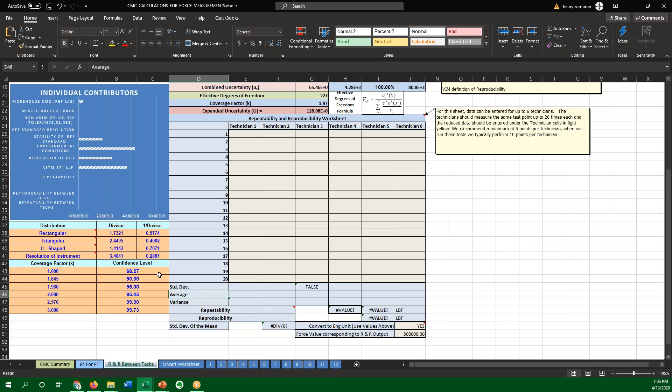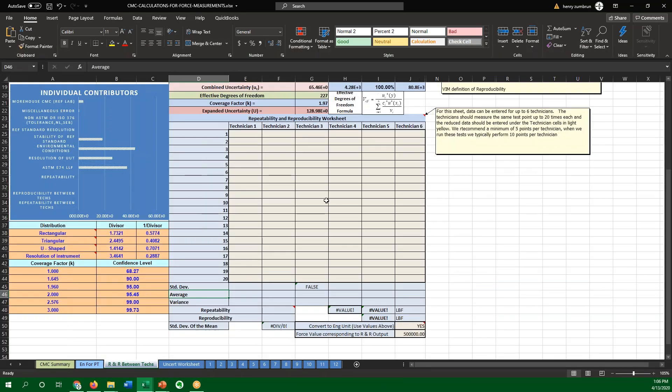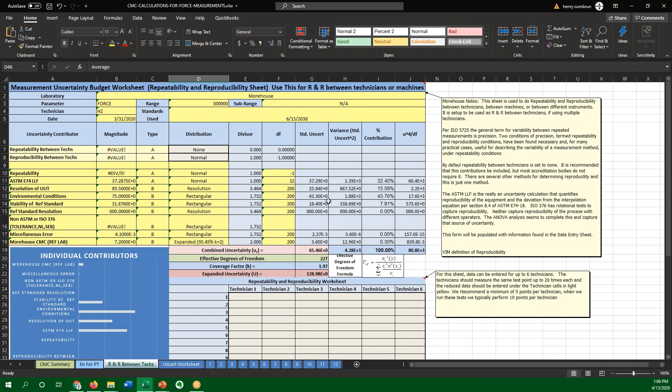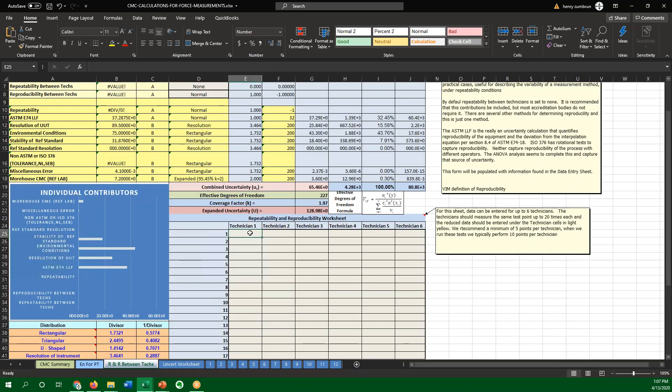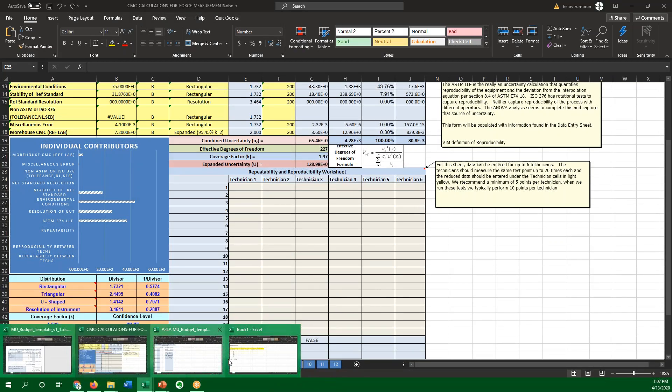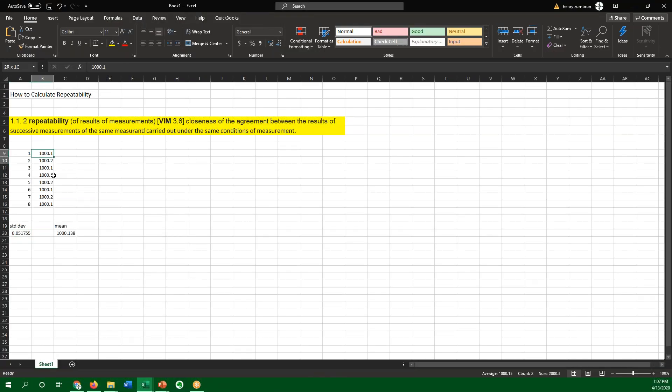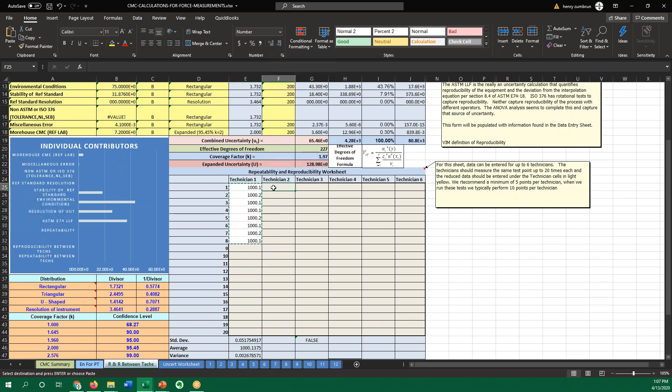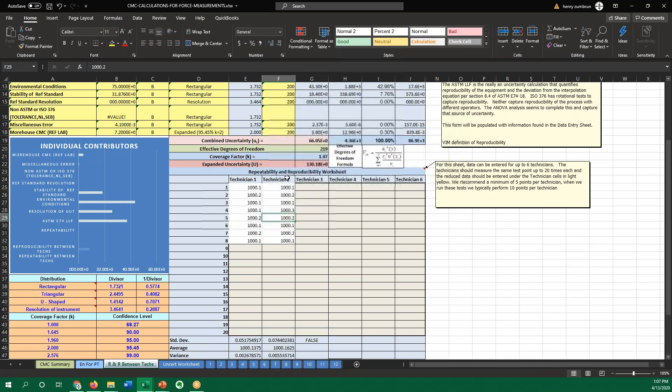Morehouse, our spreadsheet here, our uncertainty worksheet, also has a thing for repeatability. Because if you have more than one technician or if you're running multiple tests, this sheet is a little bit more robust. And, in fact, we can take repeatability, I'm just going to take my numbers here from this one. We can take the repeatability between different technicians, which requires a little bit more math here. Make a different number, 1,000.3.